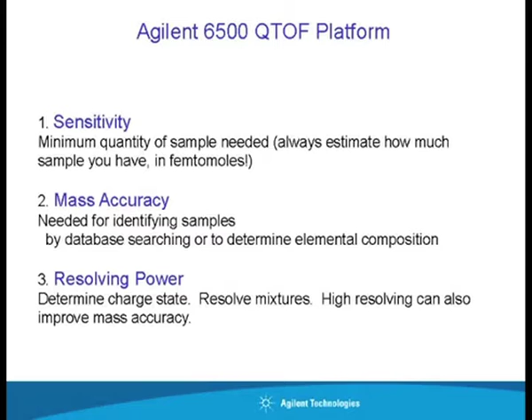Why we use QTOF, even though we have a triple quad also? We still say that for proteomics we need a time of flight type of instrument. Why so? Because of three reasons. One is sensitivity. As we understood, there is a challenge that we need to have sensitivity. Then there are two things which are very critical in the time of flight, which a quadrupole type of analyzer might miss, which are the mass accuracy and resolution.